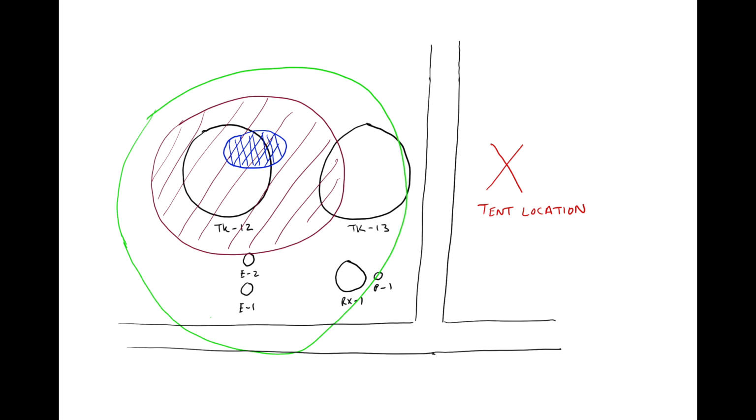Here you can see I just put together a rough little plot plan graphic if you're doing electrical classification. So pardon my drawing skills, but basically that's showing the different hash types and different marks showing the different classifications and different zones on the map, and you can see the equipment we're designating there and saying, okay, this equipment has this electrical classification. If we were doing a turnaround, we've got a little X here saying our tent location. We want to make sure, obviously, we're outside of those classifications.